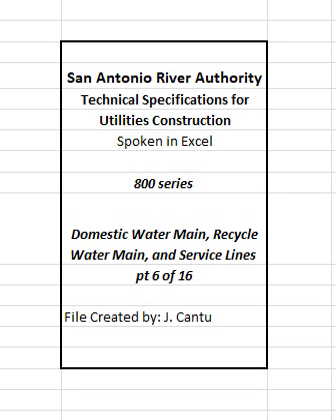4. Grade of trench bottom. The trench shall be over-excavated to a depth of 6 inches below the grade line established for the bottom of the pipe, regardless of the type of pipe. The grade line of the pipe shall then be met by the addition of a layer of approved selected material as directed.